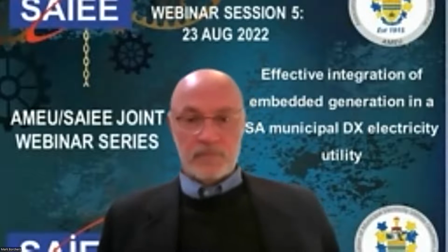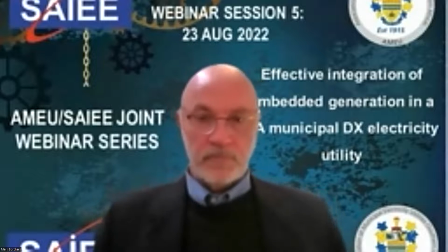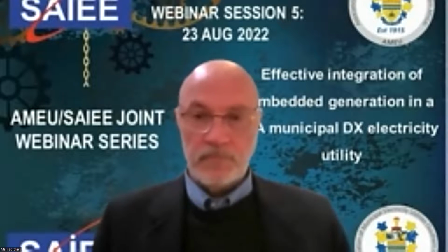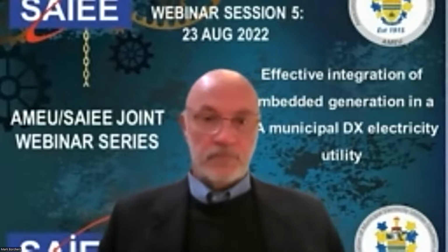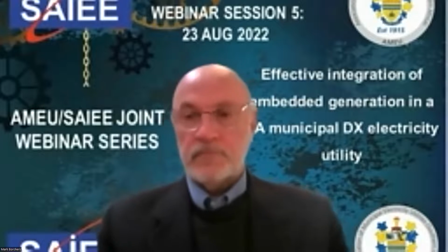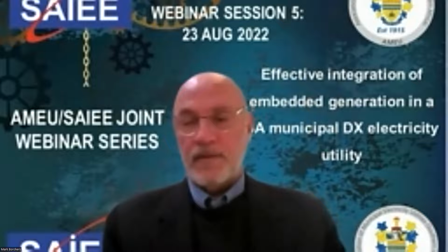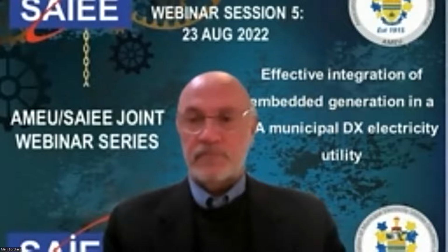But of the studies that we've received so far, there isn't any that came back showing a negative impact on the grid. Most of the suggestions will probably be on the export, because some of these generators will export, especially during weekends and during December when the companies are closed. So we need to check the loading at the substation where the customer is connected. Can the loading of that substation during that time absorb the energy exported from this SSEG?